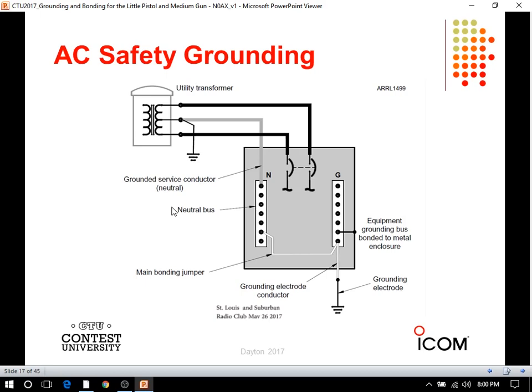Okay, the neutral comes in, it goes to a neutral bus, okay? And you'll see all the neutral wires, the white wires of your branch circuits, come back and tie to the neutral bus. And then there's a jumper called the main bonding jumper. And it goes over here to this separate bus where all the bare wires go. And so that's the grounding bus. So this is also tied directly to the metal enclosure, and that's supposed to go to the grounding electrode for your service entry. And that can be one or two ground rods. It's supposed to be outside the house. This is what safety grounding connects to, right here. That's the common point.